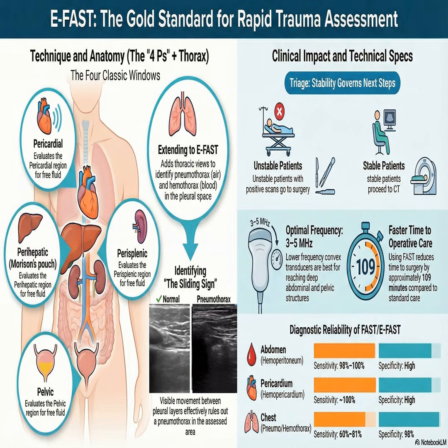But selecting the correct probe is only the baseline. A surgeon has to manipulate the knobology dynamically. Oh, knobology is huge. You have acoustic power adjusting the voltage to the crystals, depth controls to center your target, and focus to converge the waves at specific tissue planes. And then there's gain, which is notoriously misunderstood. Very much so. I see residents crank the master gain all the time when an image is dark. But gain isn't altering the power of the sound waves going into the patient. It's just adjusting the amplification of the electrical signal returning to the machine.